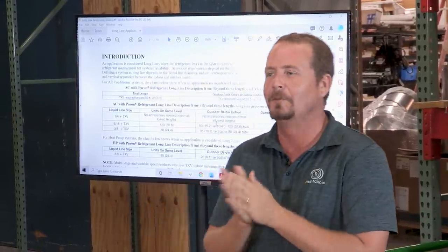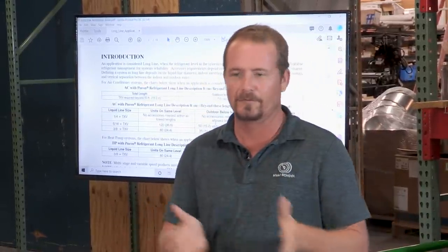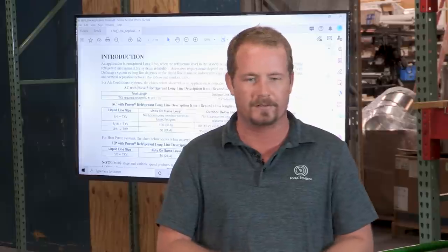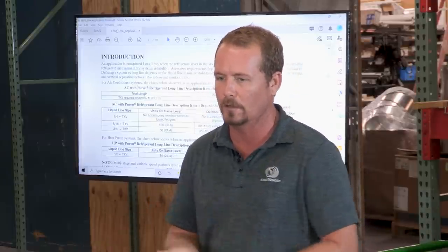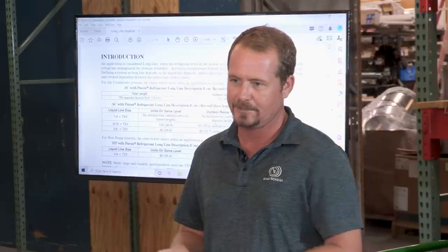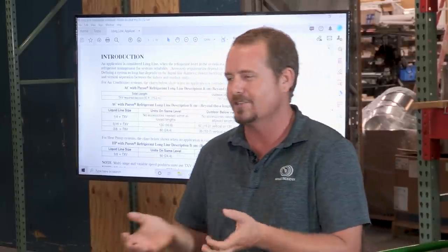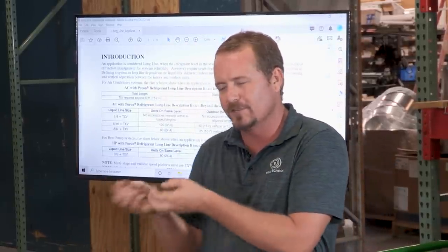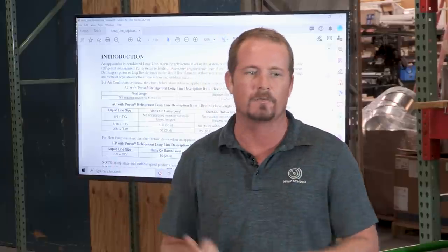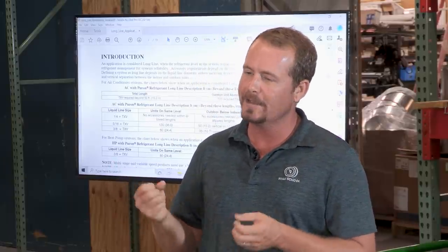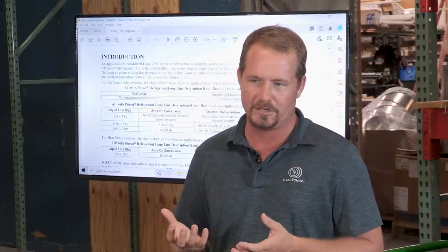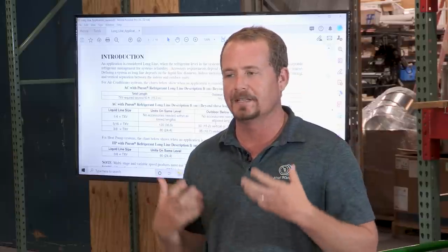Okay. Good time. So, we don't want to have liquid refrigerant. Now, when we say liquid refrigerant entering the compressor, we don't mean a full column of liquid. That's not going to happen, right? It's still going to be mostly gas. There's going to be a little bit of liquid in it. Some compressors can handle more liquid than others, and it has to do with how much is left. Because if there's a tiny bit of liquid refrigerant and it enters that really hot crankcase, in some cases it's going to flash off before it really causes much damage. But as that liquid begins to saturate that oil more and more, it gets worse and worse, right?